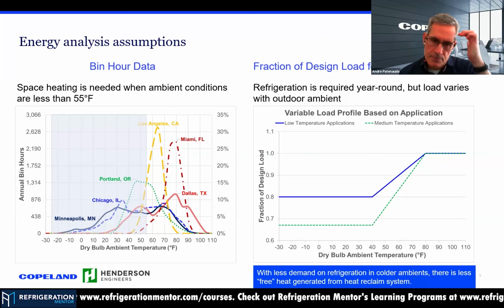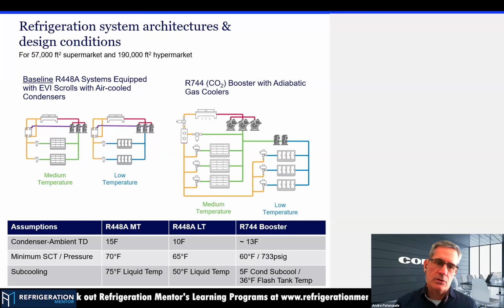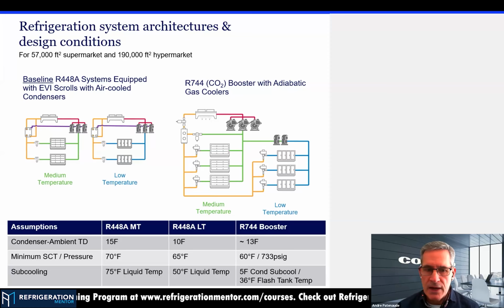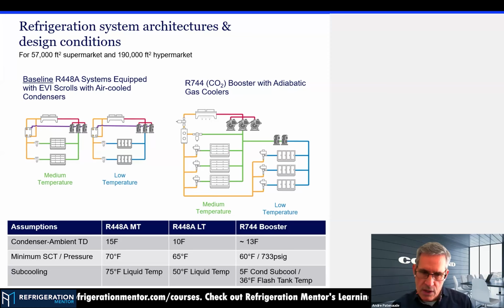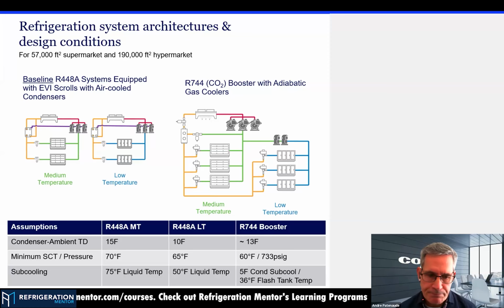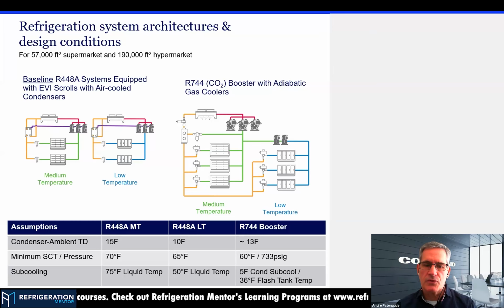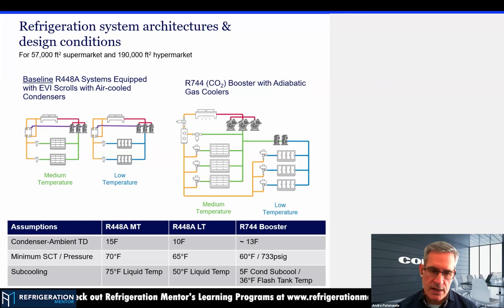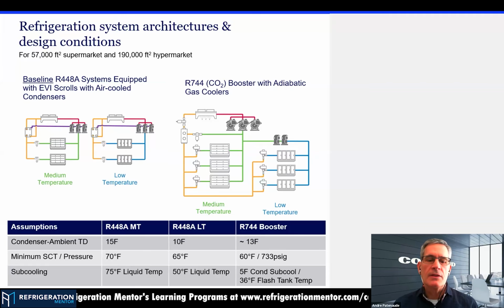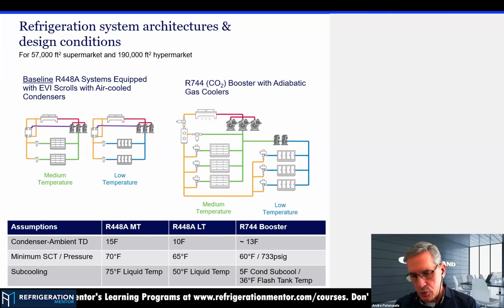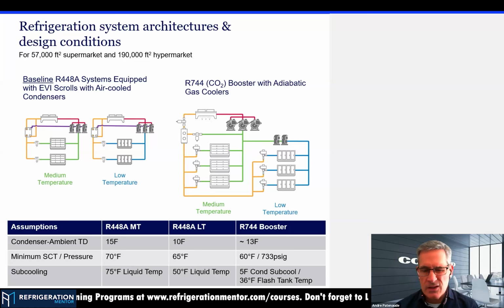So the next one, really now we're looking at architectures. A lot of us in the audience kind of get the system on the left for a supermarket and a hypermarket, a medium temp with EVI, enhanced vapor injection. So you're providing some subcooling of the liquid, medium temp and low temp. You can see at the bottom our assumptions for 448 medium temp, TD on the condenser 15 degrees. On the hot summer day, we've got, winter, we've got a minimum 70-degree condensing. In the winter, we'd see about 60-degree liquid. In the hot summer, we get about 75-degree liquid.